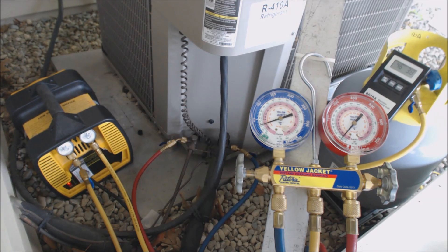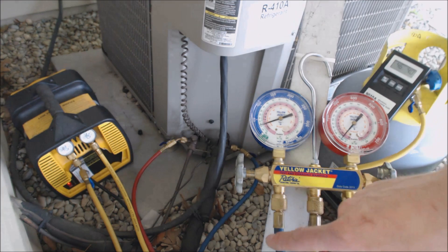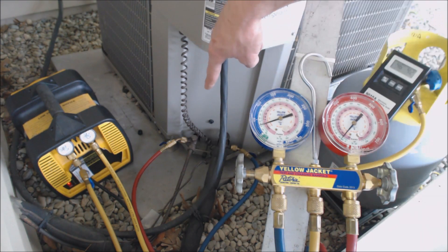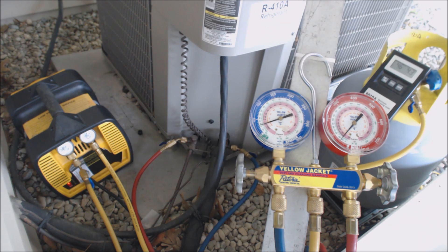Hey, this is the AC Service Pack and today what we're looking at is recovering the refrigerant out of a 410A unit. We have both of our hoses attached — our blue hose attached to the suction line and our red hose attached to the small line, which is the liquid, that's the high side.